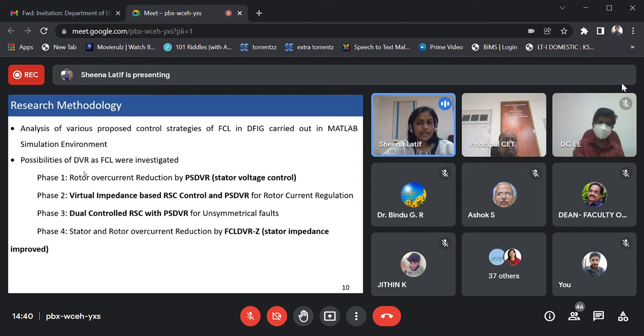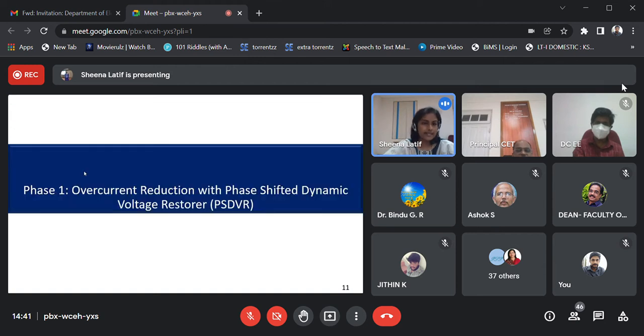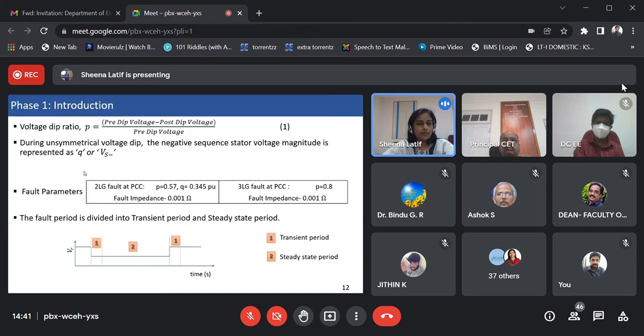In the second phase, this PSDVR method is combined with a software technique of virtual impedance-based RSC control. To overcome the drawbacks of this phase, a dual-controlled RSC with PSDVR for unsymmetrical faults is also proposed. And in the final phase, stator impedance improved overcurrent reduction in the stator and rotor of the DFIG is investigated. So, overcurrent reduction using phase-shifted dynamic voltage restorer.